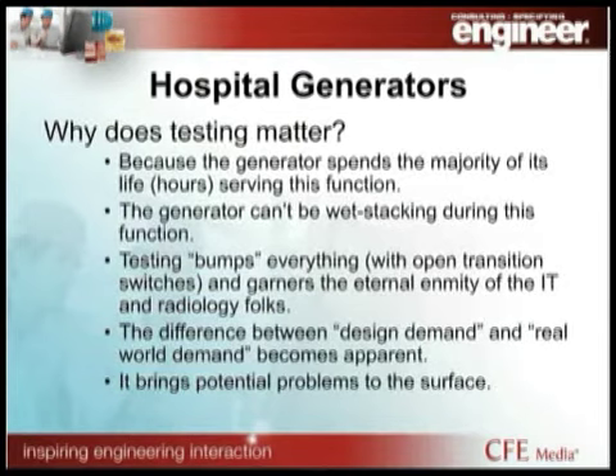So why does this testing matter, especially when we're talking about sizing generators? It's because the generator spends the majority of its life, its run hours, serving the testing function. Unless you're in Florida like me, and then the generators get a little bit of a workout. But the generator typically is tested monthly, and that is the majority of the function for that generator. The other reason testing matters is because the load that you test with must be sufficient to keep you above that 25%. That 25% requirement avoids wet stacking and gets your exhaust temperature up high enough. And testing also gets a lot of bad, dissatisfied comments from the hospital users because it bumps everything.